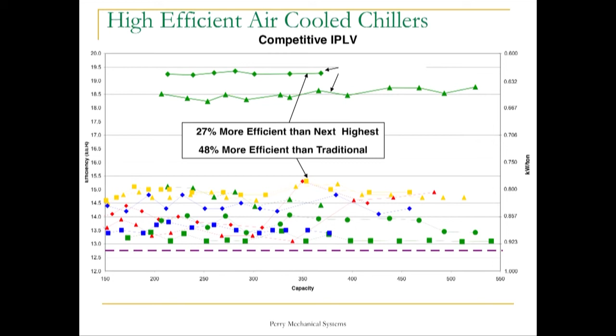The newer technologies I'm talking about on air-cooled chillers, you can see, are dramatically more efficient. You're 48% more efficient than a traditional minimum chiller, and 27% more efficient than the typical high efficiency machine. So when you get into this range, you're talking about performance that can really make sense on an air-cooled machine. Now the downside is if you tell your design team, I want a high efficiency piece of equipment, they're probably going to give you one of these right here because that's what everybody has and they don't want to rock the boat. They're just going to go with something in this range. So if you really want to go for premium efficiency, you have to make sure and stay on your design team to make sure you get what you're looking for.